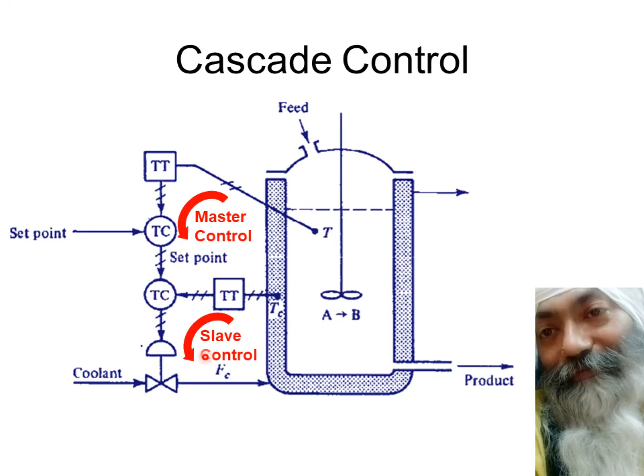Now, once again, for the final time, what I've been telling you again and again, please do not confuse. This is not a feed forward control. Cascade control, we are taking two feedbacks instead of one feedback. Two feedbacks to take care of two different disturbances. Each disturbance over here is taken care of by a feedback dedicated for that in the form of a slave loop. You can have a third slave loop and fourth slave loop and so on and so forth. Right now we are showing you only one master and one slave. This is the simplest possible configuration to give you the concept of the entire philosophy of cascade control.